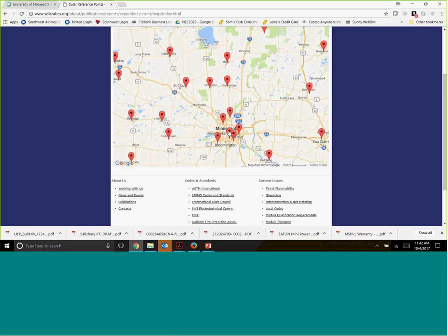The Metropolitan area, and I'll just click on the St. Paul, Minneapolis St. Paul Airport. We see -28 degrees C. Now, that doesn't mean that's the coldest temperature; it's a temperature based on statistics. It's the average minimum for all years on record. So look at all the years on record and the low for each year and then average those together, it's going to be minus 28 at the St. Paul, Minneapolis St. Paul Airport.